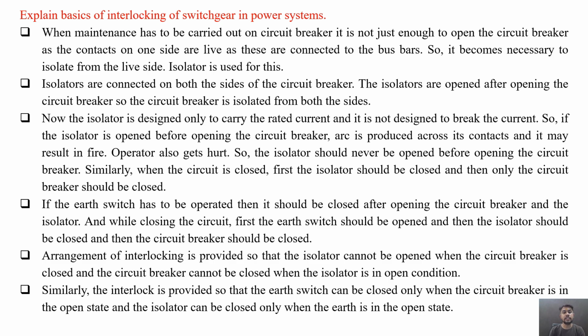Now the isolator is designed only to carry the rated current, and it is not designed to break the fault current. So if the isolator is opened before the opening of circuit breaker, arc is produced across its contacts and it may result in fire. Operator also gets hurt. So the isolator should never be opened before opening the circuit breaker. Similarly, when the circuit is closed, first the isolator should be closed and then only the circuit breaker should be closed. Otherwise, the circuit breaker is disconnected or isolated from both the sides. It is not connected with the bus bars.